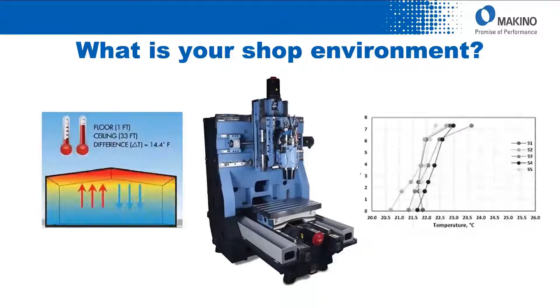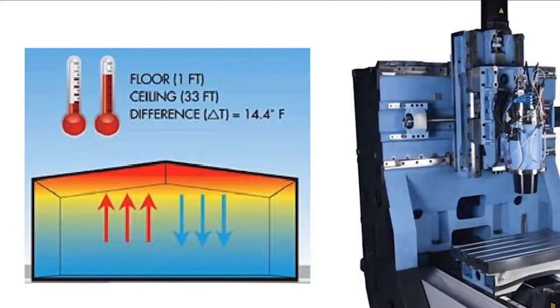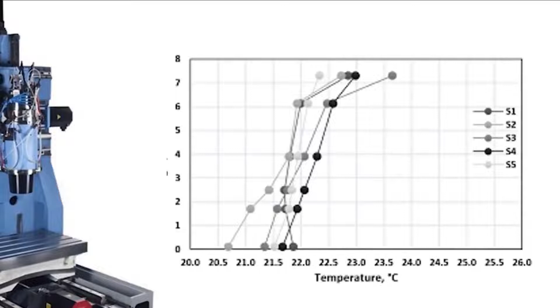Let's take a look at the vertical machining center again. As you can see on the left-hand side of the screen, that's a shop where the ceiling height is 33 feet tall. This is a plot of various points on the machine and the temperature change, and you can see the temperature is warming throughout. So in this example, in a 33-foot tall factory, you could see from the floor to the ceiling a potential change of over 14 degrees. And the thing is, it's stratified—cooler along the floor, and as you go up it gets warmer, warmest along the roof of the building.